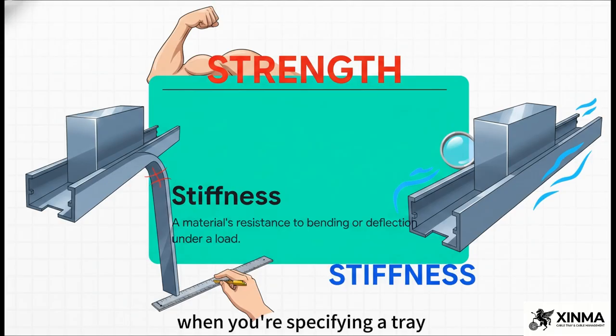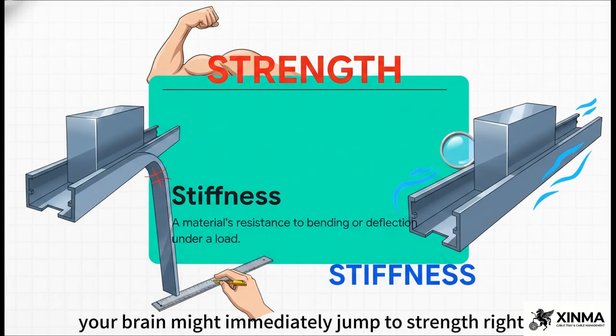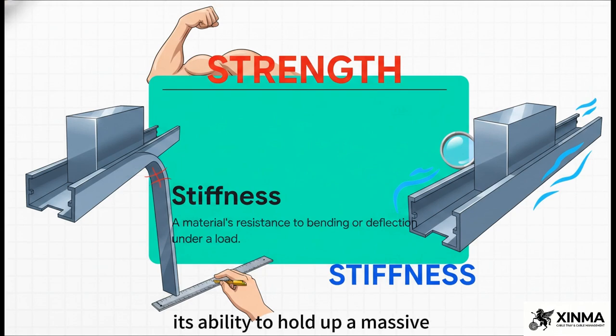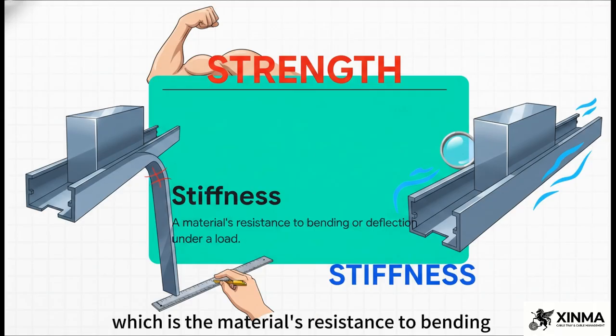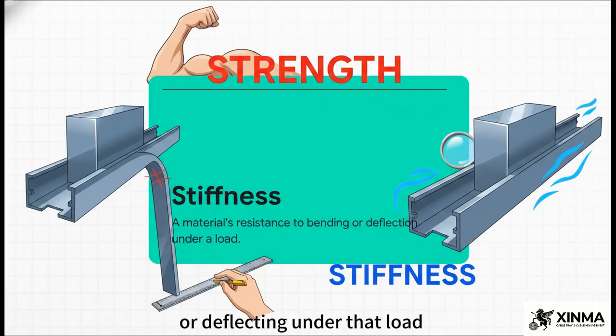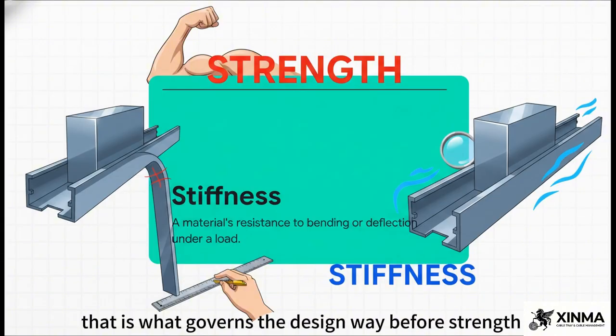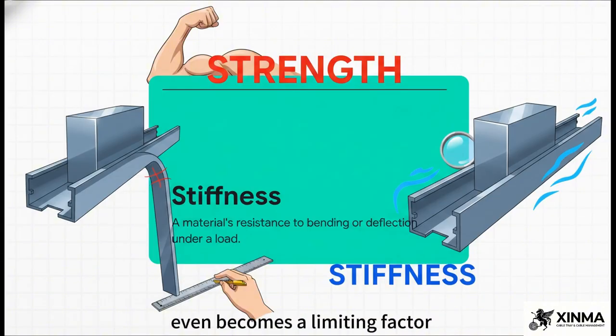When you're specifying a tray, your brain might immediately jump to strength, right? The ultimate breaking point, its ability to hold up a massive, heavy load without just snapping in half. But in reality, stiffness, which is the material's resistance to bending or deflecting under that load, is what governs the design way before strength even becomes a limiting factor.